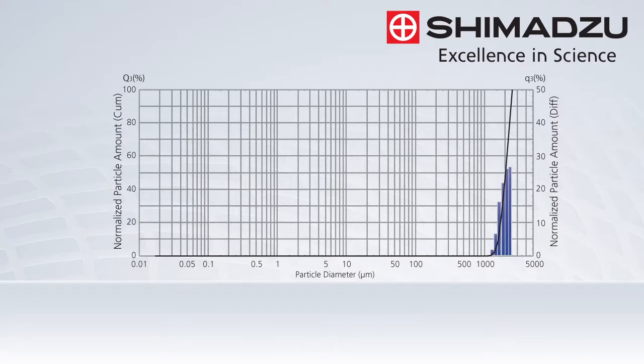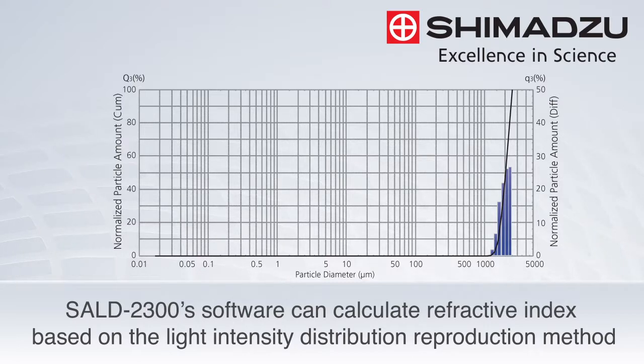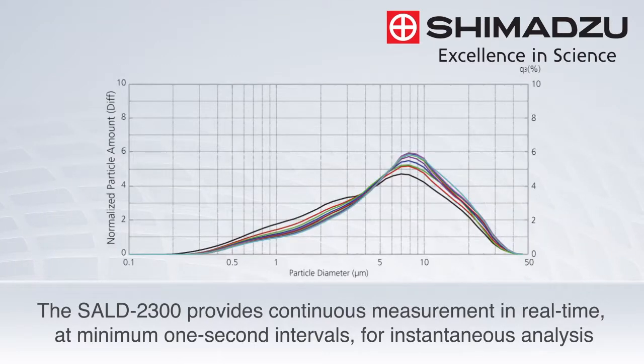Across this measurement range, the SALD2300 software can automatically calculate an appropriate refractive index based on the light intensity distribution reproduction method — the world's first software to perform this calculation. The SALD2300 provides continuous measurement in real time at minimum one-second intervals for instantaneous analysis.